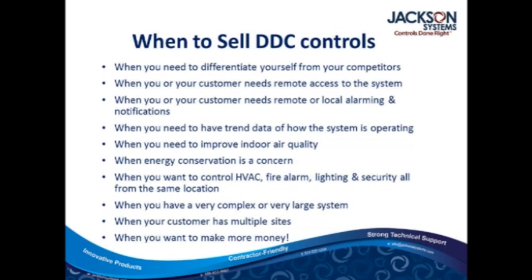It might be that you're going to use DDC controls to close the outside air while you're warming the building up in the morning for a morning warm-up period. If you're starting your rooftop unit at 5 in the morning, maybe you don't have to let the fresh air open until people start arriving at 8. All kinds of things you can do energy-wise to conserve energy with DDC that you can't really do with a typical programmable thermostat.